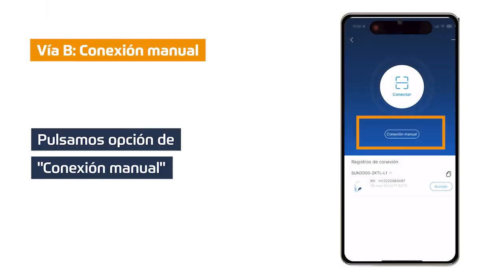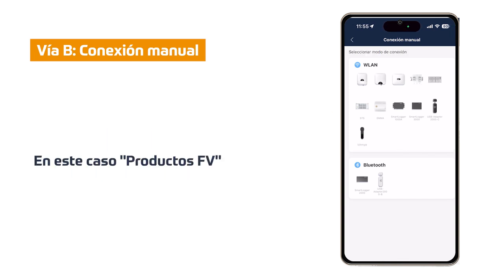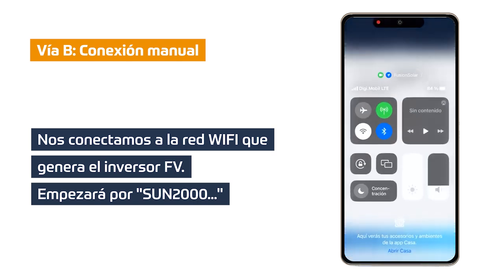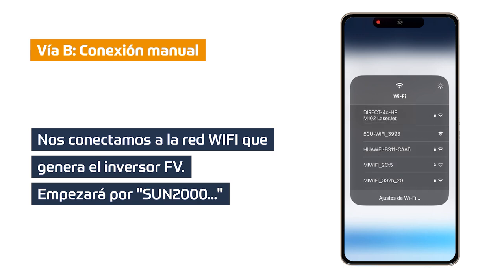Via B: We click on WLAN manual connection and configure the current LAN of our mobile device. We choose the device we want to modify its Wi-Fi network, which in this case will be FV products as it is an inverter. We must connect to the WLAN network of the inverter, which will start with SUN2000. Click on configure, activate our Wi-Fi and look for the SUN2000 network. Click on it and wait for it to connect. If it asks for a password, it will be CHANGEME (C-H-A-N-G-E-M-E). Go back and click on connect.